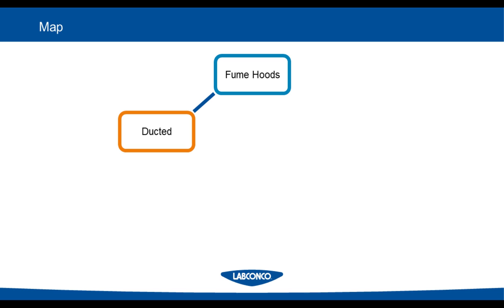Now, ducted fume hoods can come in one of two configurations. That would be the remote blower or the built-in blower models. What we're going to discuss first are the ducted hoods, and the first configuration we're going to talk about is the remote blower configuration. This is the most common type of installation. This puts the blower on the roof or somewhere outside of the building, away from the fume hood in a remote location. Hence the title of the configuration.